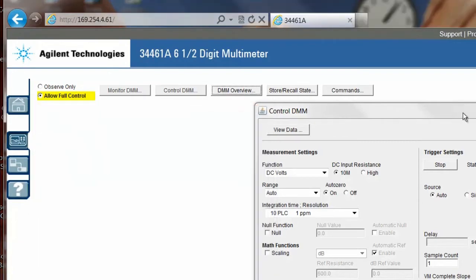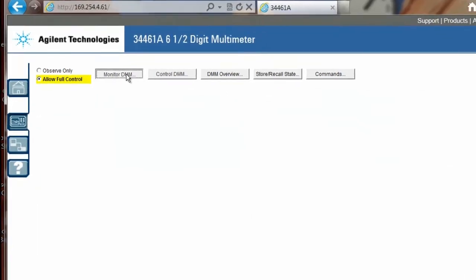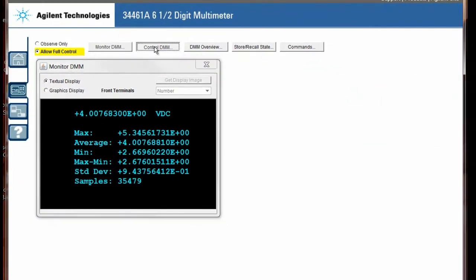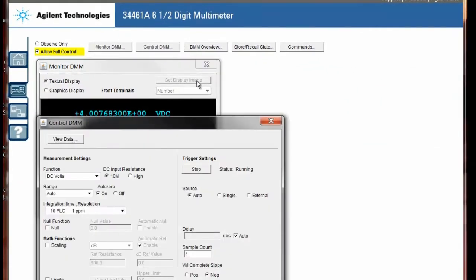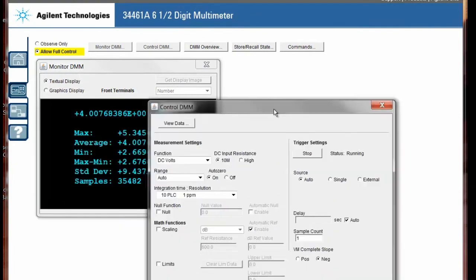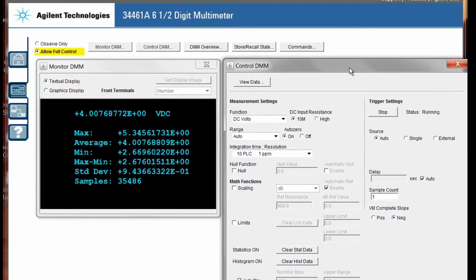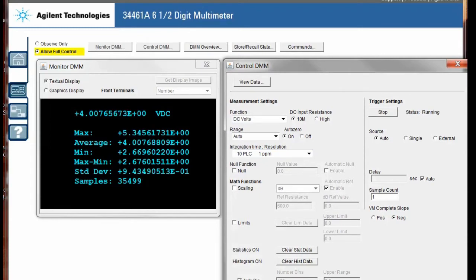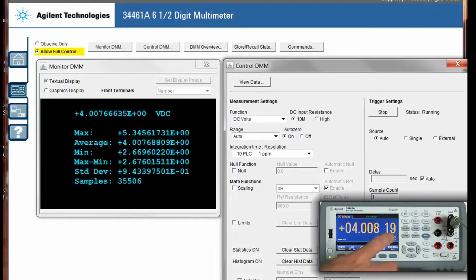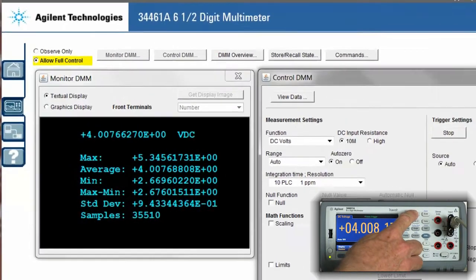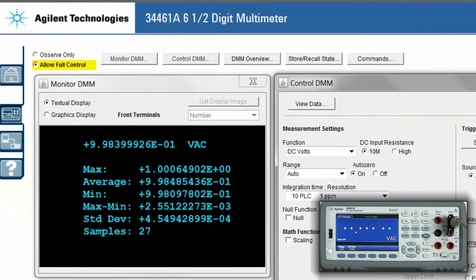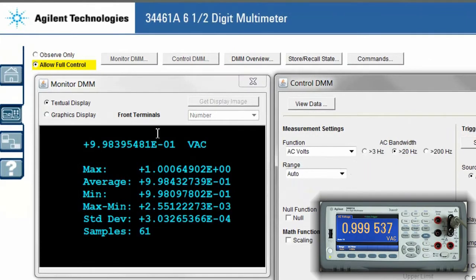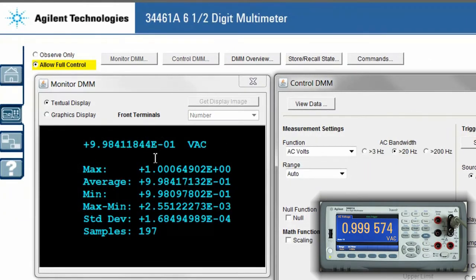I'm going to start by bringing up the first two panels in the web UI, the monitor DMM panel and the control DMM panel. So the first thing I want to demonstrate is by changing the front panel of the instrument, I'm going to switch it to AC volts.